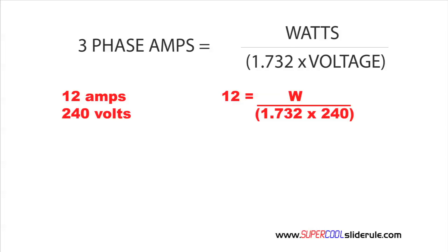So, it is 1.732 times our voltage was 240. If we do the math on this, we come out with amps are equal to watts divided by 415.68. Now, to figure this out, all we do is we multiply each side by 415.68. So, 415.68 times 12 is equal to watts.